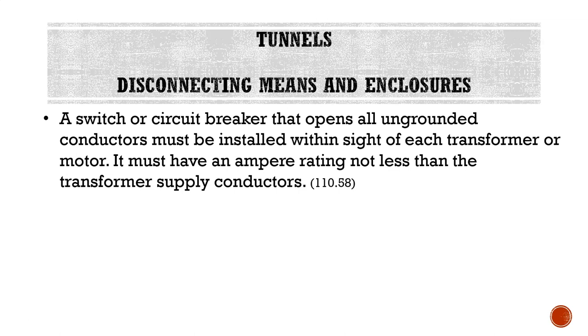Moving on, we're going to talk about disconnecting means and enclosures as they pertain to tunnels. A switch or circuit breaker that opens all ungrounded conductors must be installed within sight of each transformer or motor. So specifically for transformers and motors installed in a tunnel, we have to supply them with a disconnect switch within sight — meaning if you're at the transformer or motor, you should be able to see it. The disconnect switch must have an ampere rating not less than the transformer supply conductors.